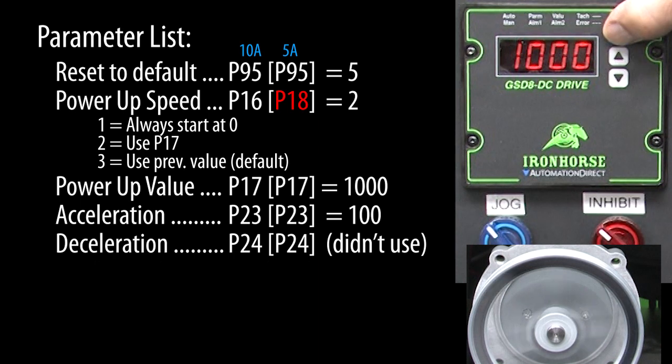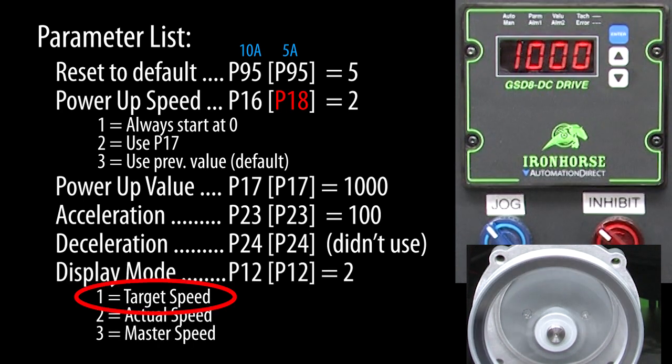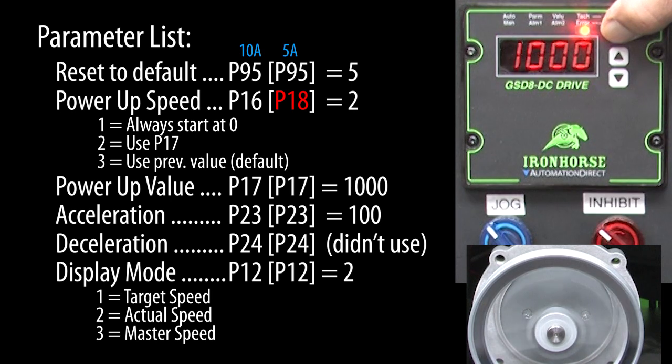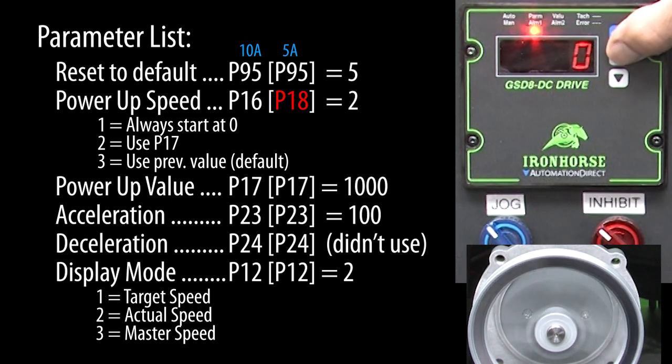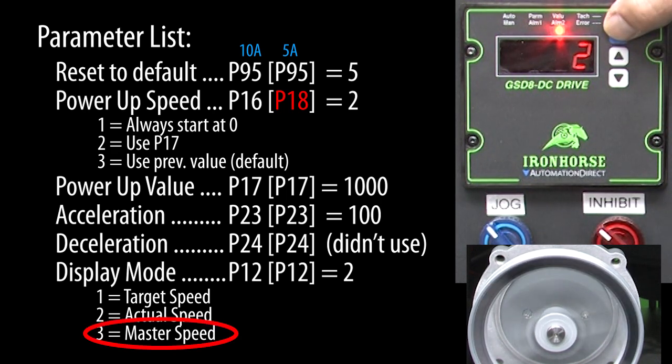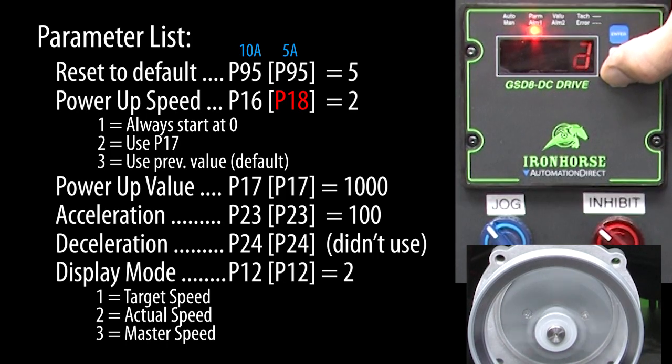Pressing enter over and over to see the actual motor RPM is a pain. Can we tell the display to show that all the time? Sure. The number we see in the display by default is the target speed. Let's change that to the actual speed so we don't have to press the enter key to see the tach. Hold the enter key for 3 seconds, scroll to parameter 12, press enter. We see we are now in value entry mode and we'll change that to a 2. Notice that you can also display the master's RPM if this drive is a follower. That's great for debugging master follower configurations because you can see if the follower is getting the pulses from the master.